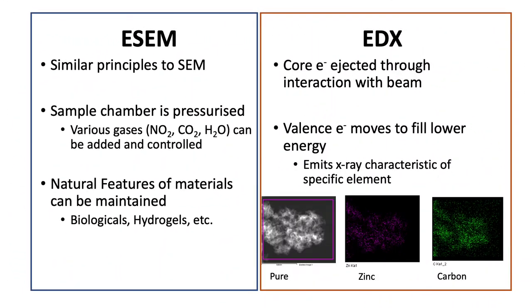So a technique was developed known as ESEM or Environmental Scanning Electron Microscopy to help address this. In ESEM, the chamber that the sample is kept in is not under high vacuum, rather low vacuum, and in some cases even humid conditions. This does negatively impact both the resolving power and the surface sensitivity of the image, but you can use it to study novel systems.